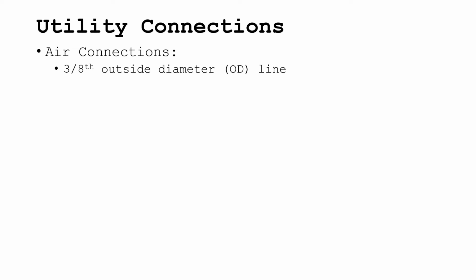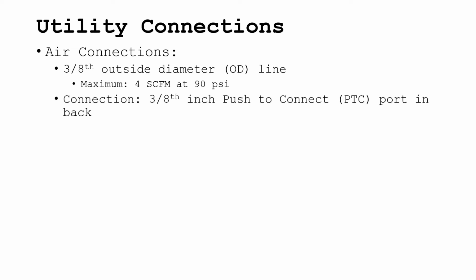Next, you will need to connect all the utilities to the Catalyst LTLF system. To connect the air connections, use a 3/8 inch outside diameter line with a maximum of 4 standard cubic feet per minute of clean dry air at 90 pounds per square inch to connect the air supply at the 3/8 inch push to connect port on the back of the system.